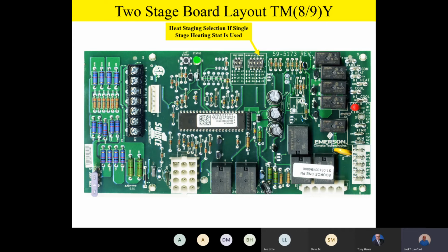Now you'll notice that there are some positions on those dip switches. If both of those switches are off, if both of them are in the up position, that's the off position. You'll notice there's another position where, if one dip switch is down and the other one is up, that's 10 minutes. You also have an auto function. If the left one is down and the right dip switch is up, that gives you auto. And then if both dip switches are down, that gives you 20 minutes.